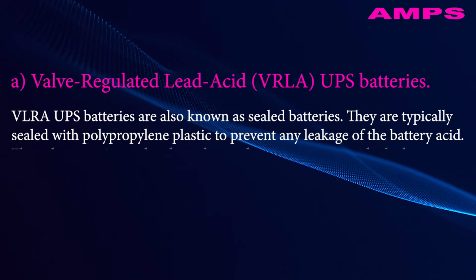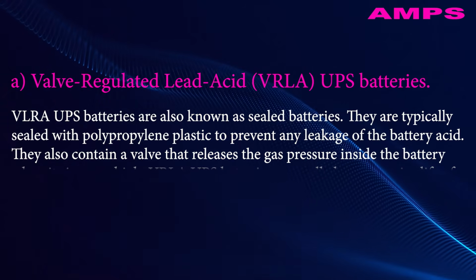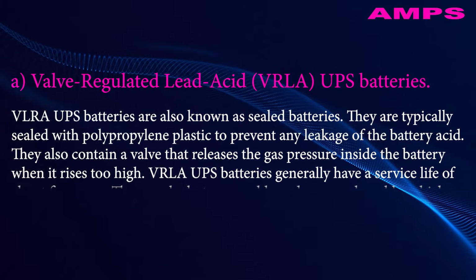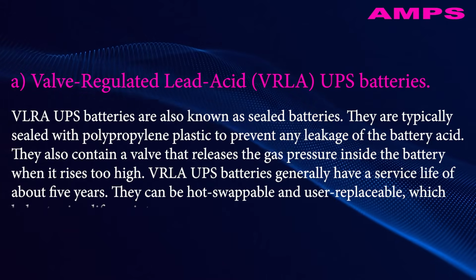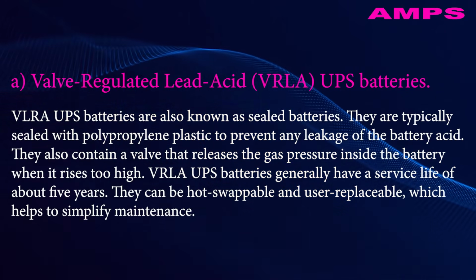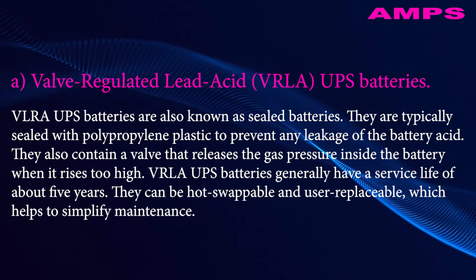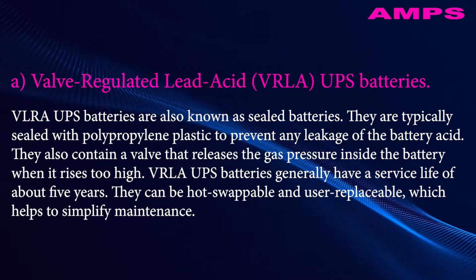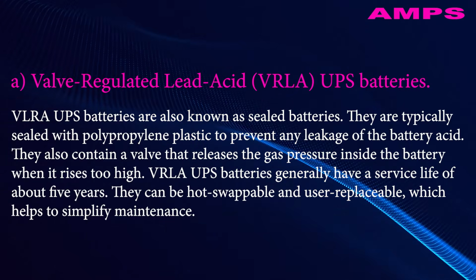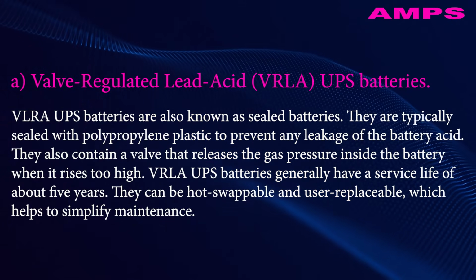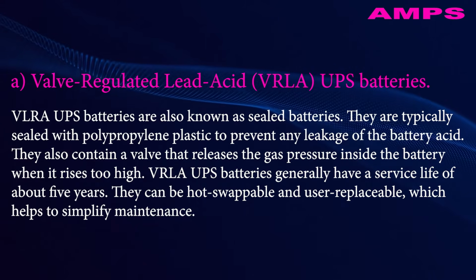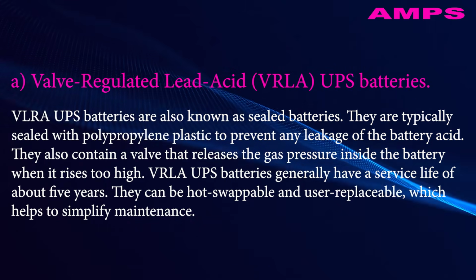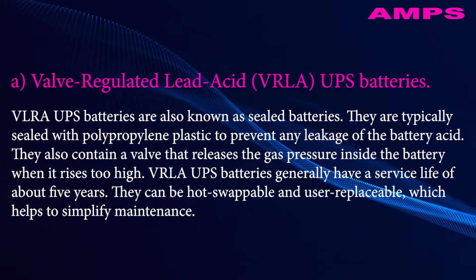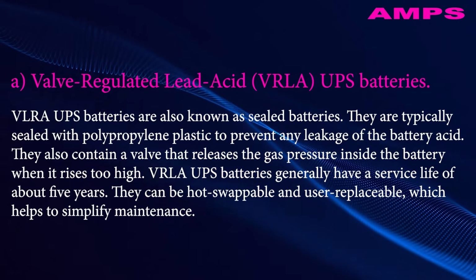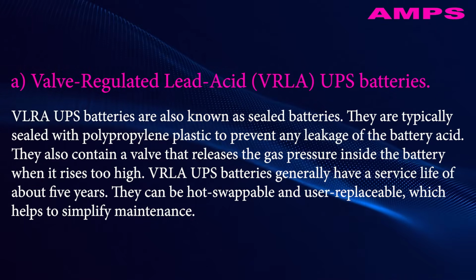VRLA UPS batteries are also known as sealed batteries. They are typically sealed with polypropylene plastic to prevent any leakage of the battery acid. They also contain a valve that releases the gas pressure inside the battery when it rises too high. VRLA UPS batteries generally have a service life of about 5 years. They can be hot swappable and user replaceable, which helps to simplify maintenance.